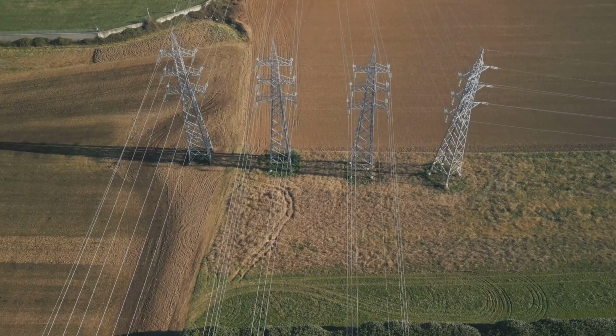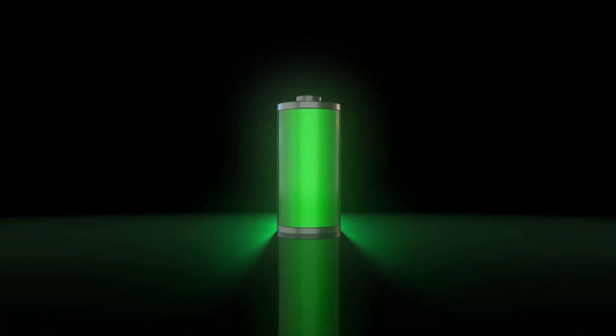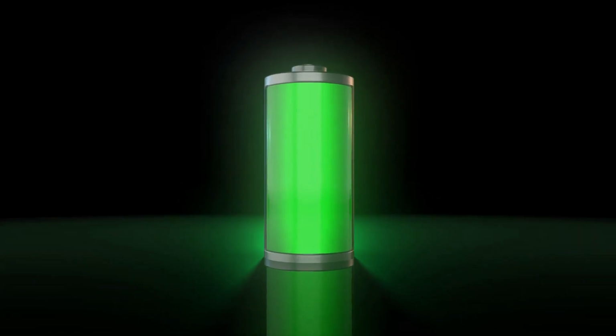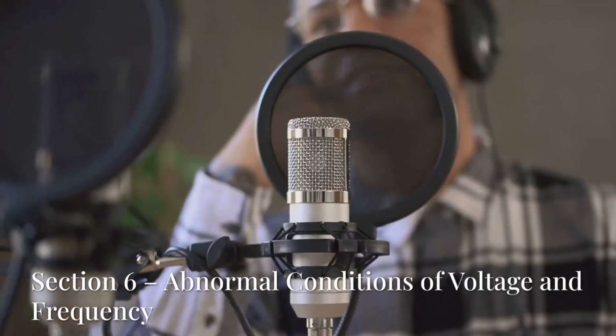Response time is another key FRT parameter. Although the standard allows up to 10 seconds for full mode response, most FRT-relevant actions, like injecting VARs or throttling watts, need to occur within 500 milliseconds to be effective. Advanced inverters often target a sub-cycle response.